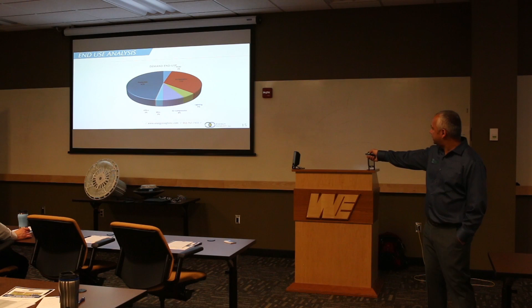Here's a good example. Somebody comes in and tells you, hey, I can save you half the energy if you upgrade your lighting. So you go to your superiors asking for funding, telling them this guy says we'll save half the energy. But guess what, lighting is only 5% of your load. If next month your production is 10% higher, that 50% savings on just 5% of your load, you will never see it on your bills.